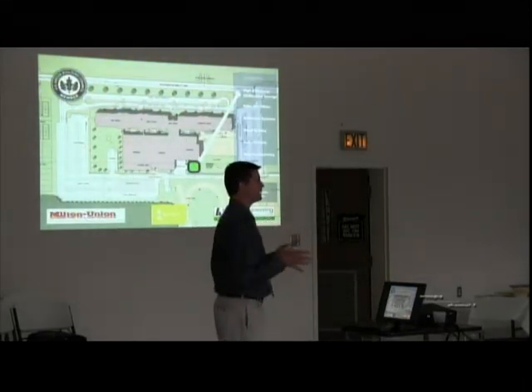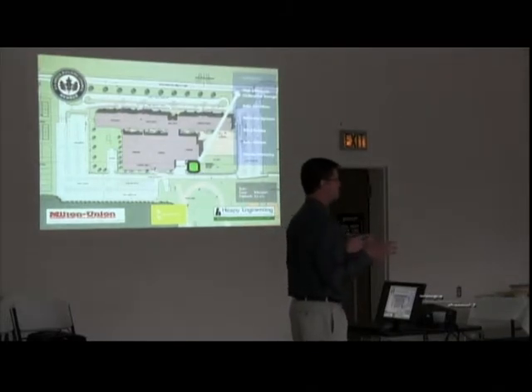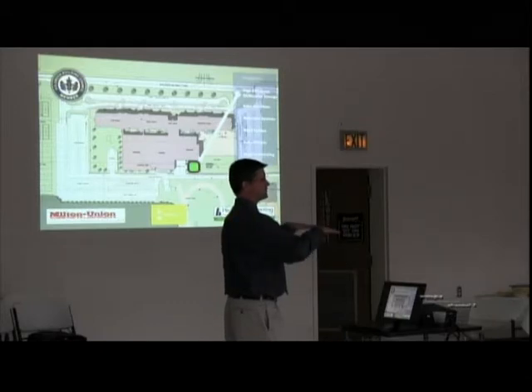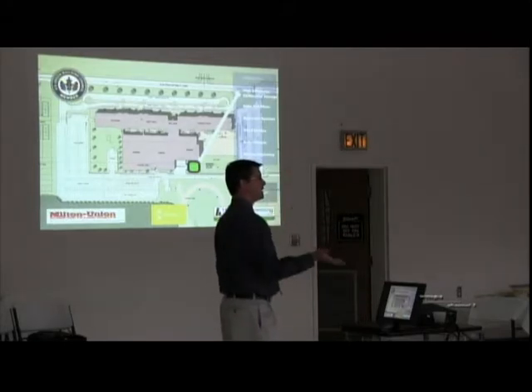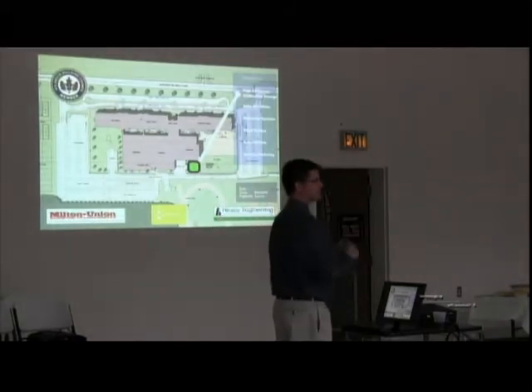On the system side, we have high efficiency air-cooled chillers. Now, that's kind of a fancy term, but basically these are essentially traditional chillers. The difference is in how they're controlled. What our engineers discovered is that these chillers operate most efficiently at 60% of total capacity. So we have 3 of these chillers in this yard, and when there's a demand for air conditioning, the first chiller comes up to 60% and stops. Then the second chiller comes up to 60% and stops. And then the third chiller comes up to 60% and stops, if demand is there. If demand is less than those capacities, then they don't turn on chillers 2 and 3. But if demand goes above that, there's a controlled mechanism that allows the chillers to perform beyond their 60% capacity.